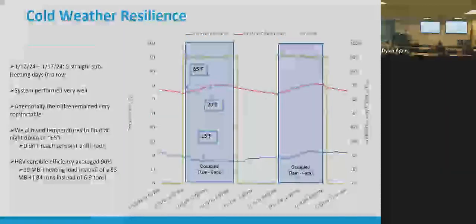And that's what we found. And this is one example, whereas 20 degrees or 15 degrees below design temp, we still let the building shut off and float temperature down at night just to see what would happen. I love doing science experiments in the real world at the expense of my own engineer's comfort. But it still maintained about 70 during the day. So we found that even with undersized systems, the building doesn't go to 60. Pipes aren't busted, especially if your heat pump at least keeps running. So most of these, maybe all of them, except for the 2 Montana ones, had no backup heat. We just sized it for 99% and called it good.